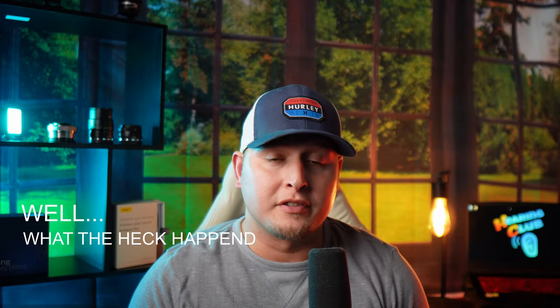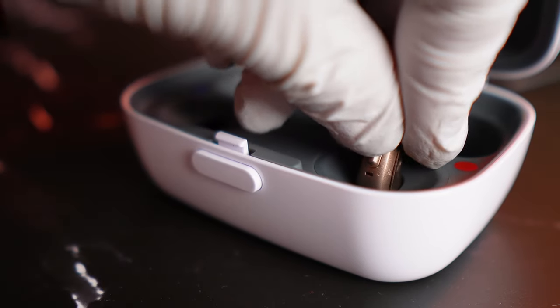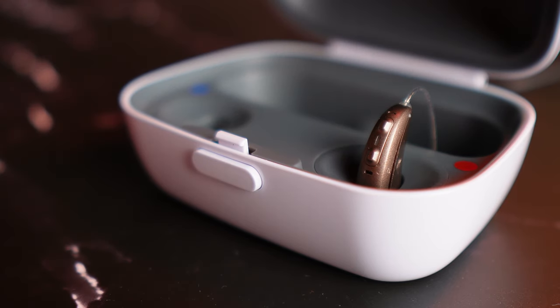So you're probably wondering what the heck happened. What happened was charging issues, unfortunately — and that is literally the only thing that was wrong with these hearing aids. We got so many returns, refunds, and exchanges, and sent them back for repair and replacement that it was overwhelming. I would say over 60% of the KS-10s we sold came back with charging issues. Sometimes it was the charger that was at fault, sometimes it was the hearing aid, sometimes it was both. It was crazy. And to this day we're still dealing with KS-10s out there that have issues. I believe an email was actually sent out to all patients who had potentially defective KS-10s.